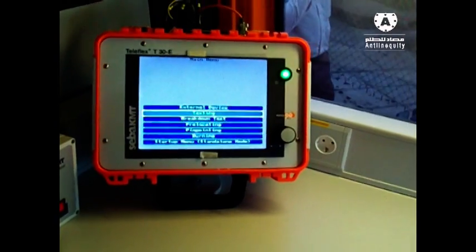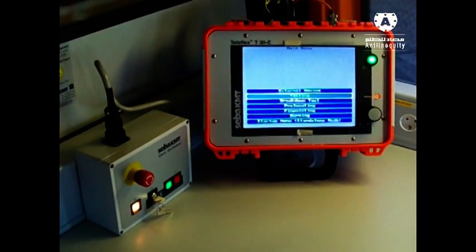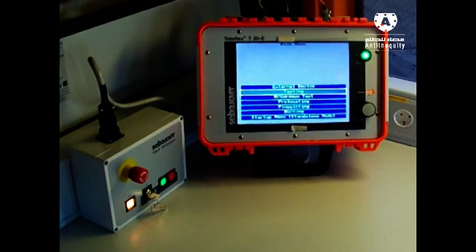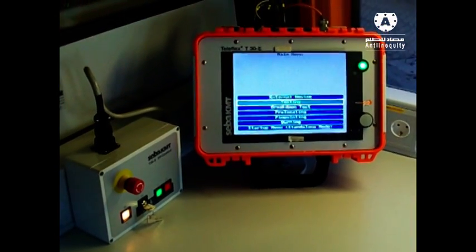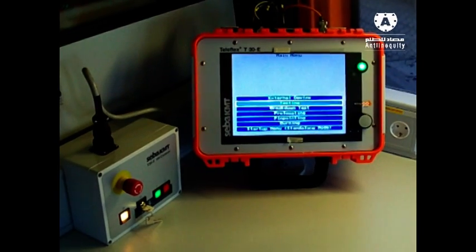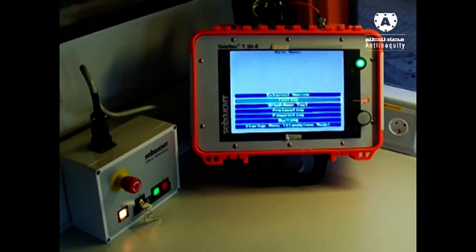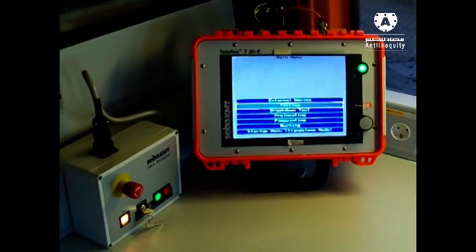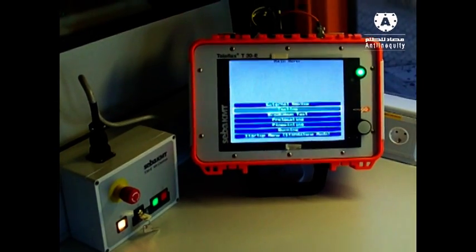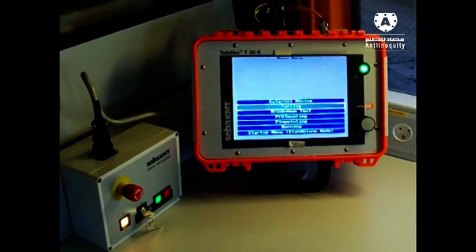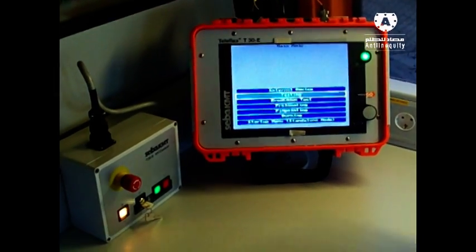After I get an idea about the failure by testing, I can now have a look inside the faulty cable with my TDR, because I want to see if it is a break on the way from the beginning to the far end, or what happens. And also I want to try to get the real velocity of our cable length to get the best results for the next step, arc reflection mode.